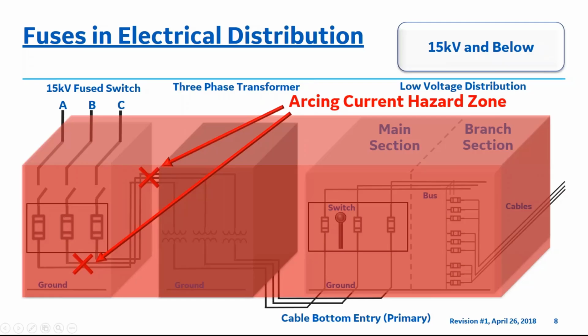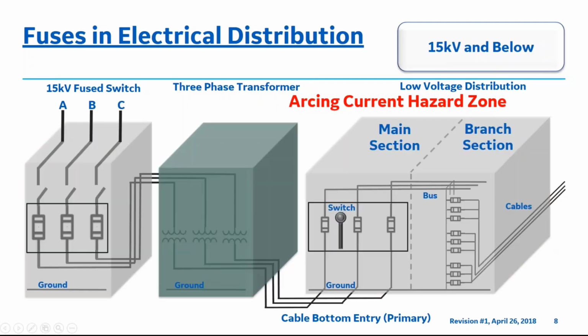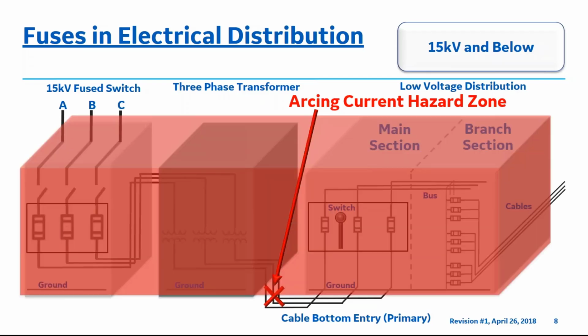The second example of an arcing fault is between the transformer secondary and the primary low voltage fuse switch. If busway or cable connections, top entry, side entry, or bottom entry shown here, between the secondary side of the low voltage transformer terminals and the fused low voltage primary in the main section are utilized, and during these arcing fault events, the hazard zone consists of this 3-dimensional area around the fault shown here.